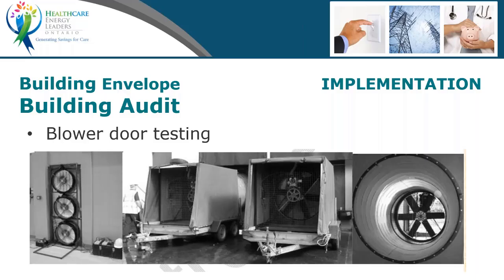Blower door testing is similar, pretty common, though less so for larger buildings, but there are ways of measuring this. Basically, they pressurize the building and measure where the air leakage is, or use a smoke pen to find the leaks. A friend of mine had his house done that way, and they're coming back after the caulking and window work is done, before finishes go back on, to retest and make sure the improvements are fully effective. So it's a matter of testing and retesting.